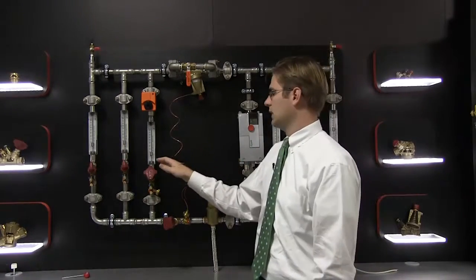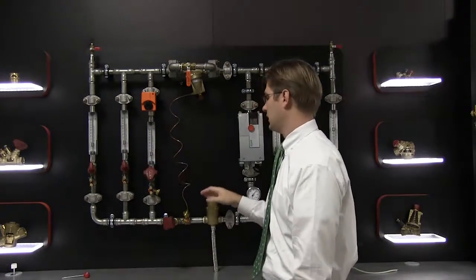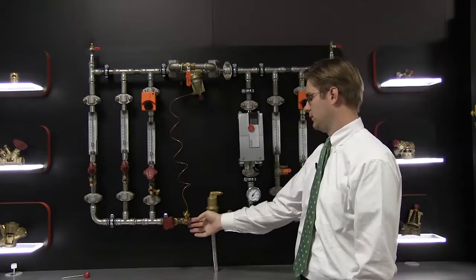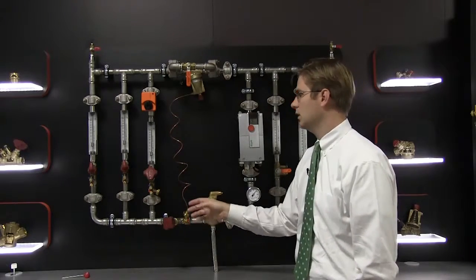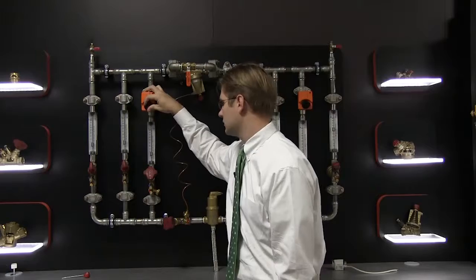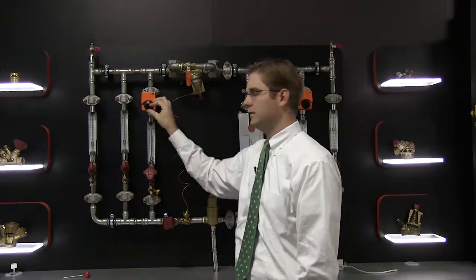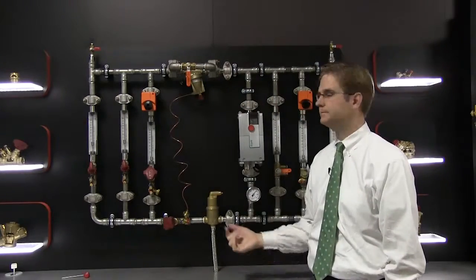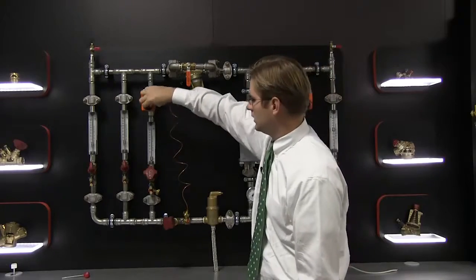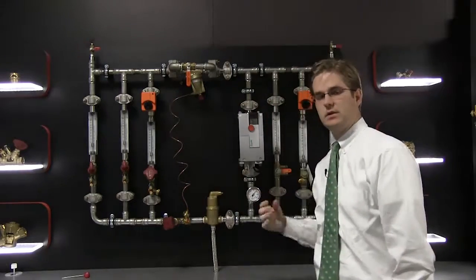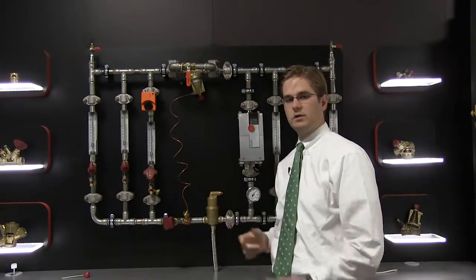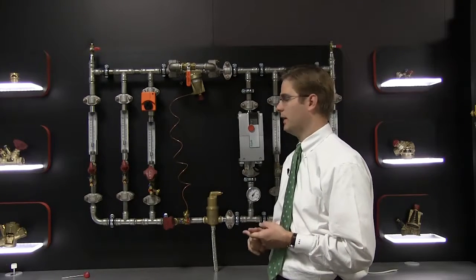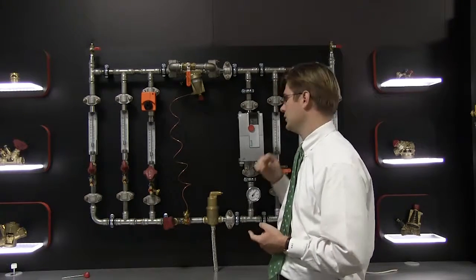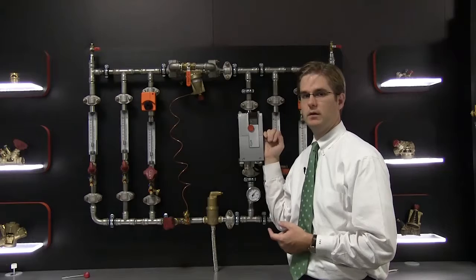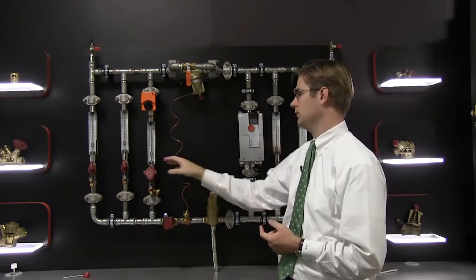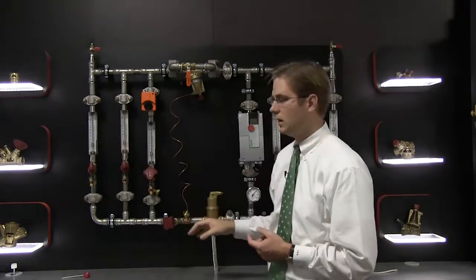Not only will they maintain 1 GPM if I increase the pressure from outside of the branch, but even if I go and I close one of these valves off, they'll still maintain 1 GPM. What this is doing is providing energy efficient delta T back to the boiler or chiller and reducing your pump electricity usage by reducing the overall flow rate.